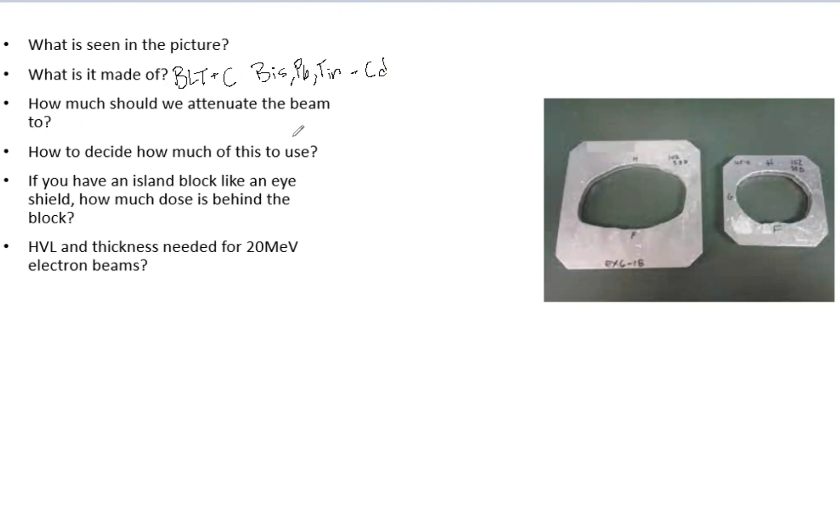So how much should we attenuate the beam to? We want to attenuate this beam that we are blocking with the Cerrobend block to around 5%. So that means the beam is 5% as strong as it was initially after it passes the Cerrobend block. For example, for a 6X, now granted this is photons, a lot stronger, a lot deeper penetration, we're going to need somewhere on the order of 8 cm of Cerrobend for that. That's a whole lot. Thankfully, most of the time we use these for electrons. So you're going to need a lot less.